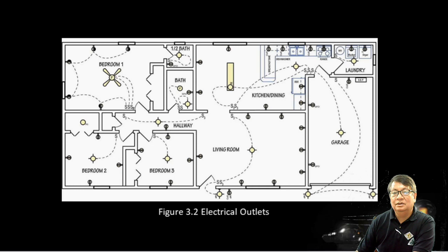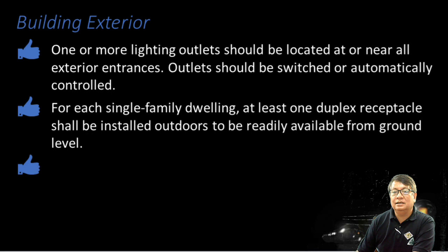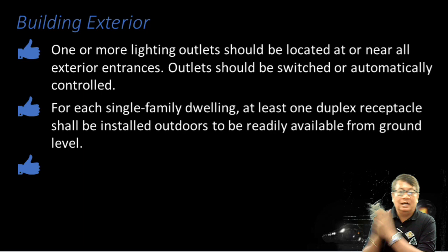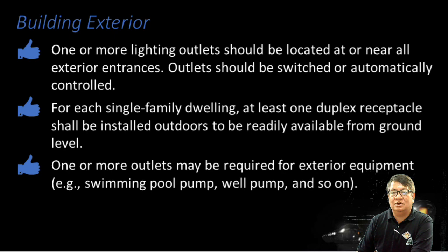Ito pong finished design. Building exterior, one or more lighting outlets may be located, no? For a single family dwelling, okay, at least one duplex convenience shall be installed outdoors to be readily available from ground level. So, pwede rin nating lagyan ng outlet or convenience outlet outdoors para mayroon din tayong magagamit sa labas, no? Pero at least one duplex receptacle lang po. Huwag natin paramihan. Okay, one or more outlets may be required for exterior equipment, like for example, doon sa mga swimming pools.